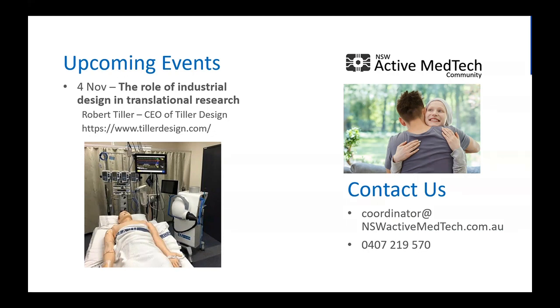Yeah, if I may add the last plea for medical device engineers, just to read the essential requirements before they do anything else. And they have to read the new one for the MDR now, which is maybe 3 times as long. But by reading that essential requirements document, Annex 1 in the directive, or now in the new MDR, it really opens the eyes of engineers to what to look for, what to do, and where to find the answers that lead them to which standard they need to read.